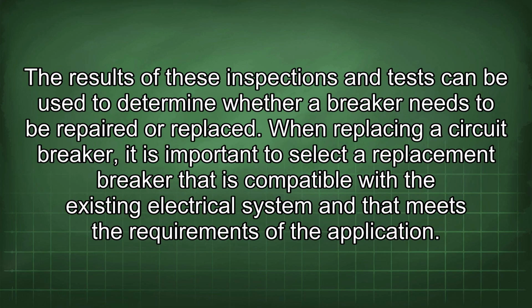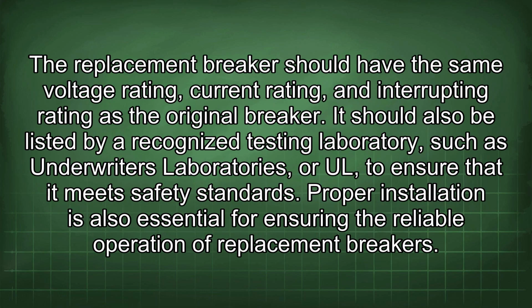The results of these inspections and tests can be used to determine whether a breaker needs to be repaired or replaced. When replacing a circuit breaker, it is important to select a replacement breaker that is compatible with the existing electrical system and that meets the requirements of the application. The replacement breaker should have the same voltage rating, current rating, and interrupting rating as the original breaker. It should also be listed by a recognized testing laboratory, such as Underwriters Laboratories or UL, to ensure that it meets safety standards.